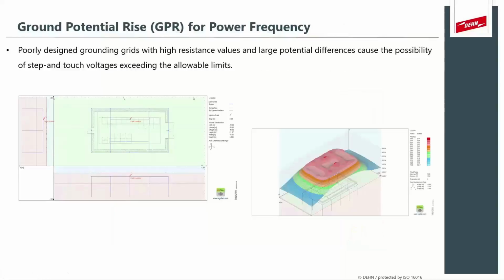Now, poorly designed grounding grids will not ensure that we have an equipotential plane, and that will start causing step voltages and touch voltages because we're not ensuring the same voltage throughout the system. If we have our same grid shown previously and we just remove some of the meshed conductors, you can start seeing on the results these voltage peaks, and there's not that beautiful equipotential plane of the same voltage all across as people walk. So if someone had to stand on these very red points and the more pink points, they would experience a very high voltage difference that can actually cause current to flow through the body and electric shock.